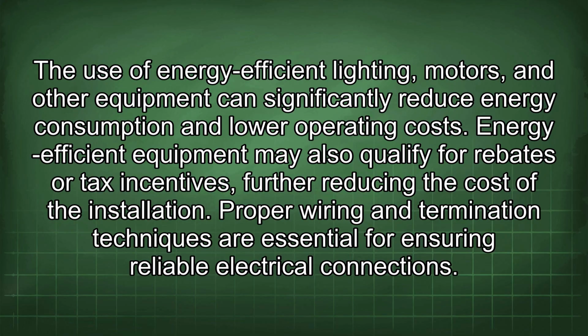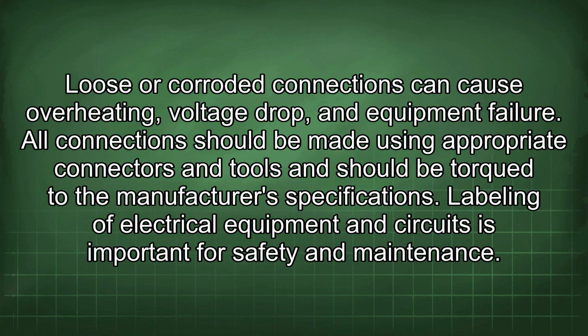Energy-efficient equipment may also qualify for rebates or tax incentives, further reducing the cost of the installation. Proper wiring and termination techniques are essential for ensuring reliable electrical connections. Loose or corroded connections can cause overheating, voltage drop, and equipment failure. All connections should be made using appropriate connectors and tools and should be torqued to the manufacturer's specifications.